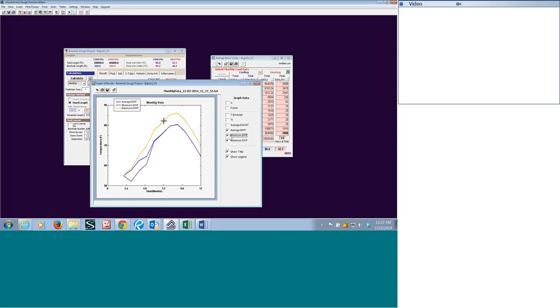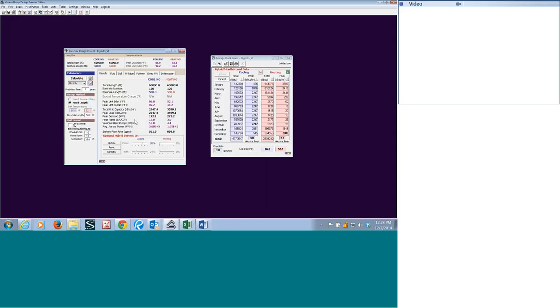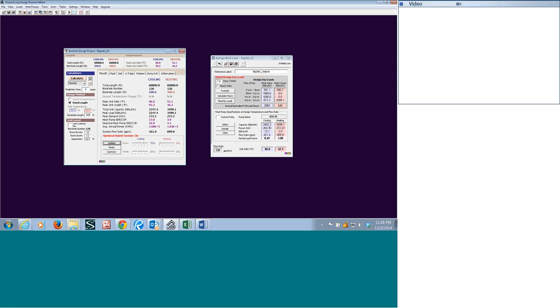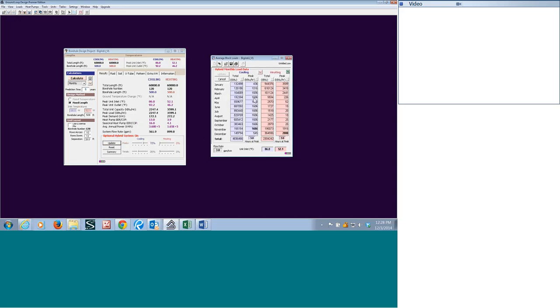So just for a 1 year projection, we're only showing a little past 85 degrees and not for very long. So what we're going to do here, for those of you who are not convinced heat creep does not occur, we're going to add a little more. Go back to 5. I'm going to take this to 70% off of the peak load. And we'll talk about some auxiliary cooling strategies to help make sure that everyone sleeps well at night. So now we've definitely shaved a lot of peak off this thing. 70% off the peak. We're down to 1,686 kBTU per hour as a peak from March through November.